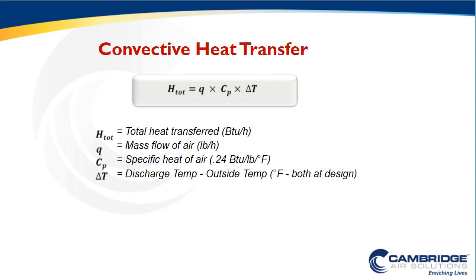So this simple equation here is what governs our entire industry. And what it says is that the convective heat transfer, or the total heat transferred, is equal to the mass flow of air times the specific heat of air times the discharge temperature difference. Again, if you'll notice, that equation does not say volumetric flow. It says mass flow. Yet, how often in our daily operations, in our daily calls, in our daily designs, are we typically thinking about volumetric flow?